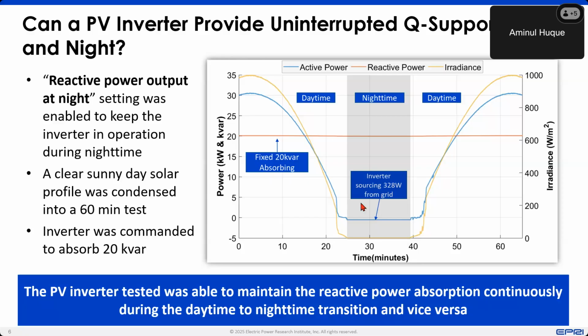And then of course, we also want to capture how much active power is actually needed during the nighttime to stay on and provide the reactive power support. That's another thing, but I'll cover that in more detail in the next slide. So what you are seeing, basically, is the active power, of course, going from 31 kilowatt gradually to 0. And during this night period when irradiance is 0, active power is close to 0, but actually not 0, it's negative. I'll explain that next. But then next morning it wakes up and goes back to normal operation.